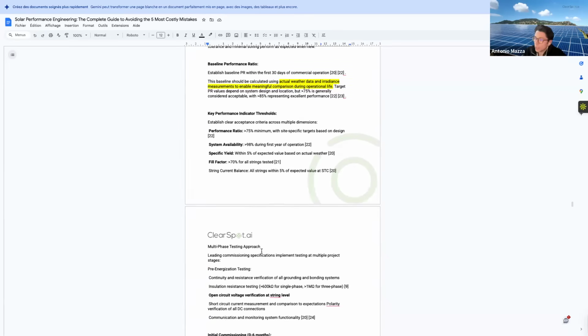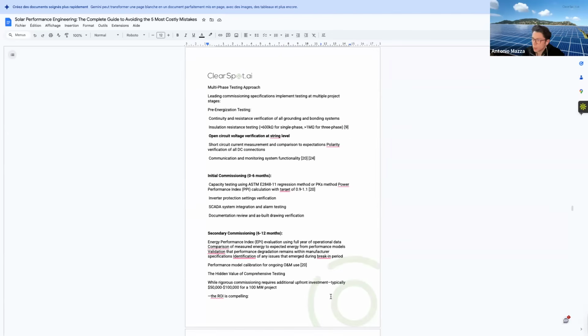Multi-phase testing approach, leading commissioning specification. We know there are multiple project stages. Pre-energization testing: continuity and resistance verification of all grounding and bonding systems, insulation resistance testing, open circuit voltage verification at string level. Initial commissioning: capacity testing with regression models. There are some approaches, such as a PPI index, where for calculation we target 0.9 to 1.1. Also inverter protection setting verification, SCADA system integration, documentation review.